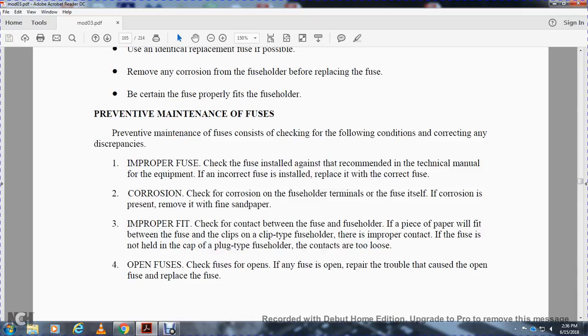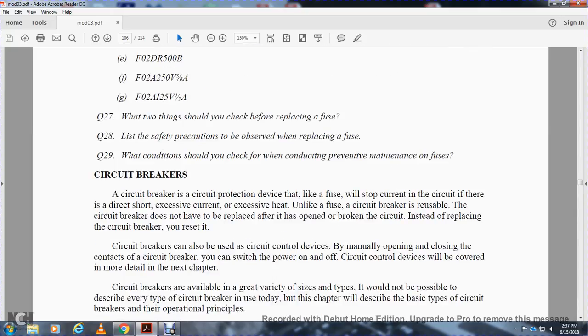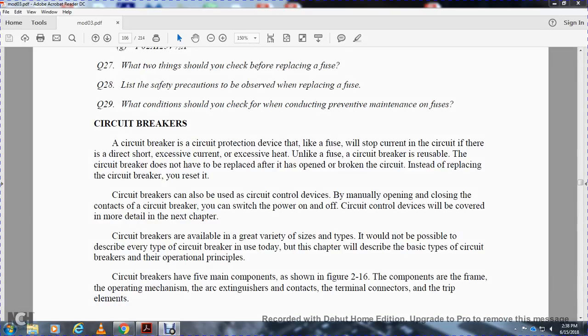Preventive maintenance of fuses: preventive maintenance of fuses consists of checking conditions and correcting any discrepancies. Improper fuse: check the fuses installed against those recommended in the technical manual for the equipment. If an incorrect fuse is installed, replace it with the correct fuse. Corrosion: check for corrosion on fuse holder terminals and on the fuse itself. If corrosion is present, remove it with fine sandpaper. Improper fit: check for proper contact between the fuse and the fuse holder. If a piece of paper can fit between the fuse and the clips of the clip-type fuse holder, then contact is improper. All right, we're going to cut the tape here at circuit breakers, and then it should be a shorter reading for Chapter 2.